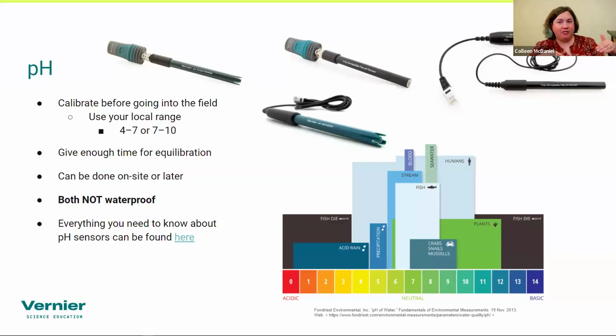pH is another one like temperature. You're going to want to give it time to equilibrate. What I sometimes recommend is, when you have a pH sensor, you're storing it in a pH 4 potassium chloride solution. And that is how it should be stored. But often pHs of water are going to be a little closer to that neutral range. So if you want to cut down the time of waiting for that equilibration to take place, I typically soak my pH sensor in a pH 7 buffer about 3 hours before I go out and do the readings, or the night before. And that just gets the sensor primed in more neutral territory, so it can equilibrate a little bit faster when you go out and do readings.